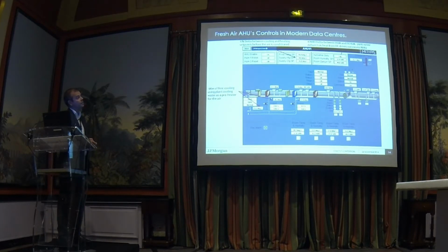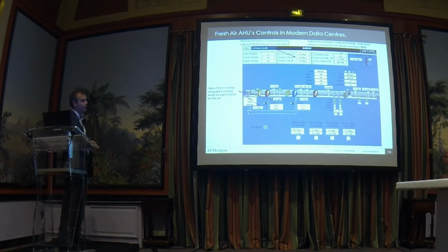So 80% dehum, 37% RH, 7% the RH added humidity. That number's quite high because these steam humidifiers have to work flat out all winter, and they're about 15.5 kilowatts each. So you've got two machines, so you're doing 30 kilowatts just about all through winter, just trying to keep the humidity above 28. When I did this screenshot, it was probably about spring and autumn or something like that, so the humidity was pretty well self-sustaining there just from the outside air temperature coming in and the humidity.